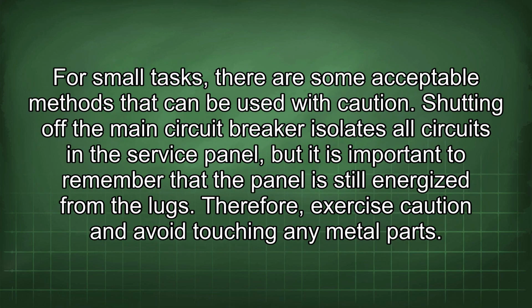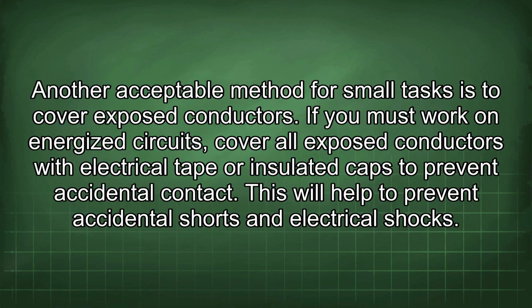For small tasks, there are some acceptable methods that can be used with caution. Shutting off the main circuit breaker isolates all circuits in the service panel, but it is important to remember that the panel is still energized from the lugs. Therefore, exercise caution and avoid touching any metal parts. Another acceptable method for small tasks is to cover exposed conductors. If you must work on energized circuits, cover all exposed conductors with electrical tape or insulated caps to prevent accidental contact. This will help to prevent accidental shorts and electrical shocks.